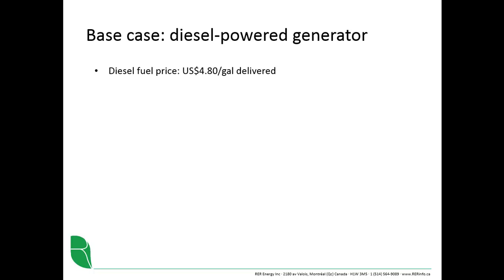Diesel fuel costs $4.80 US per gallon delivered to this site. That's a little over $1.25 per liter. We're going to need to be able to supply the peak load with the diesel-powered generator, so we will size it at 10 kilowatts. A diesel-powered generator for prime power operations might run around $10,000 US installed.